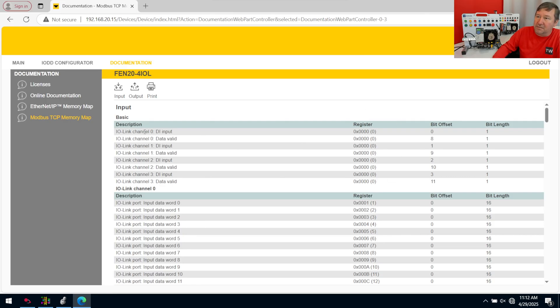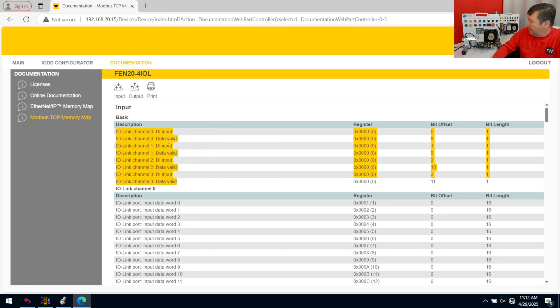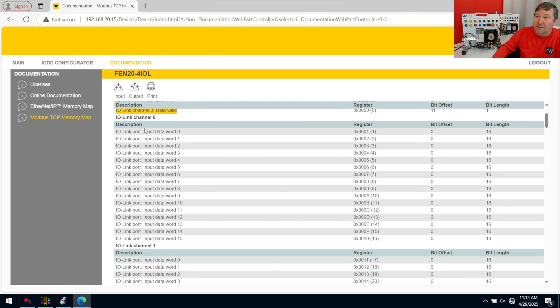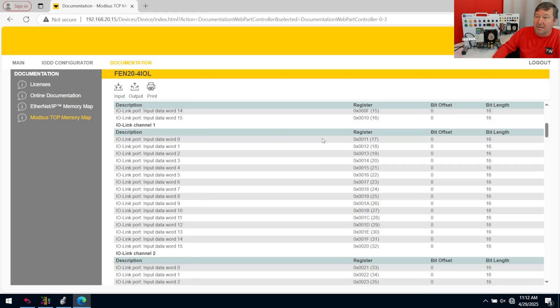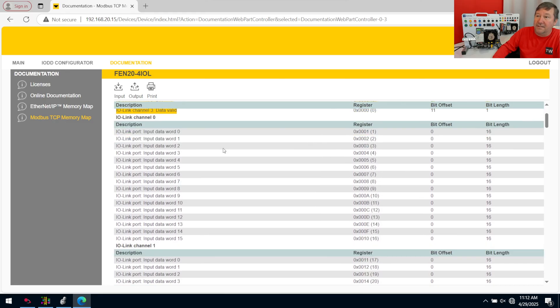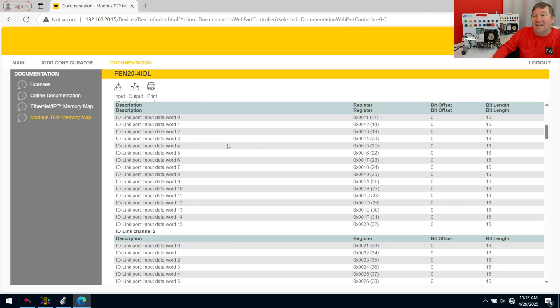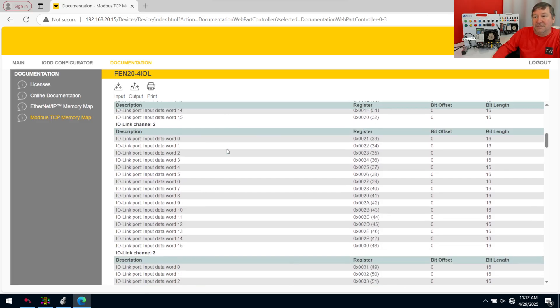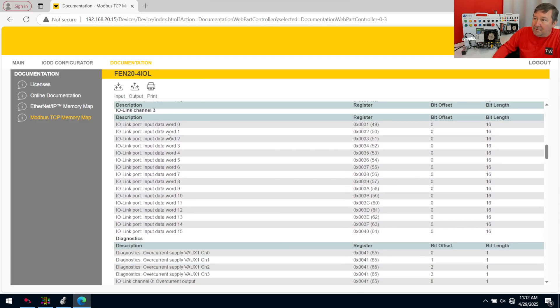Now, after that, it can get a little hairy about how much data should you read. Now, in my opinion, on this particular Turk, I definitely want zero because that includes our discrete inputs, which is our capacitive and inductive procs. We definitely need channel one because that's going to give us our laser distance sensor. I'm sorry. That's channel zero gives us our laser distance sensor. Channel one, channel two. And mainly, we need the encoder. So we need down to 50.